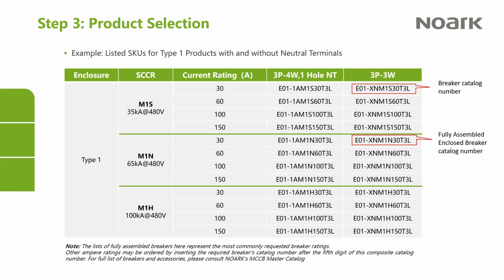And because they're so high up in the power system, they have to be able to withstand much higher interrupting ratings, and they also have to be able to withstand a fault for a longer period of time, so that it allows the breaker closest to the fault to trip first. So those are the primary differences between a molded case breaker and a power circuit breaker. We offer both, and in some ways they can be used interchangeably at the higher ampacity ranges. For example, the A25 has a 600 amp rating, but if it needs to go into switchgear, or if you need a draw-out version, that would be your product.